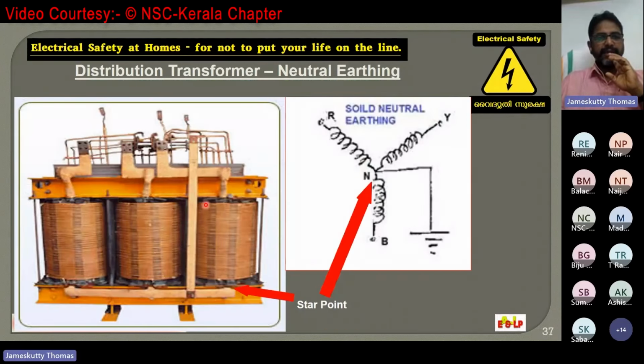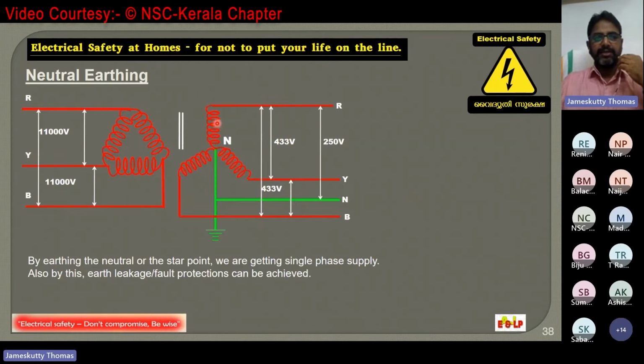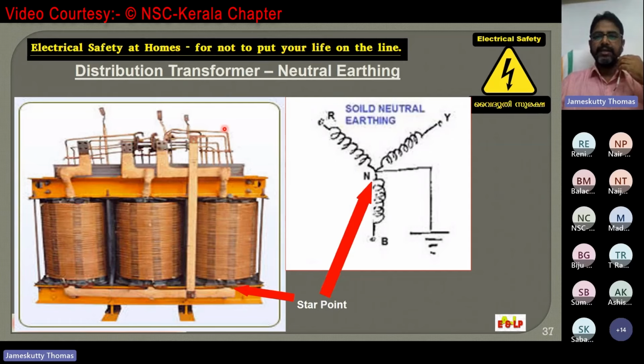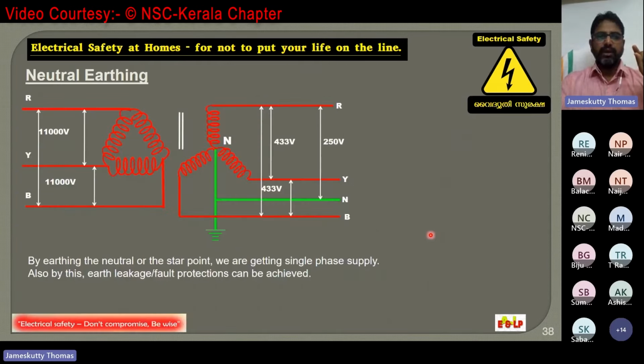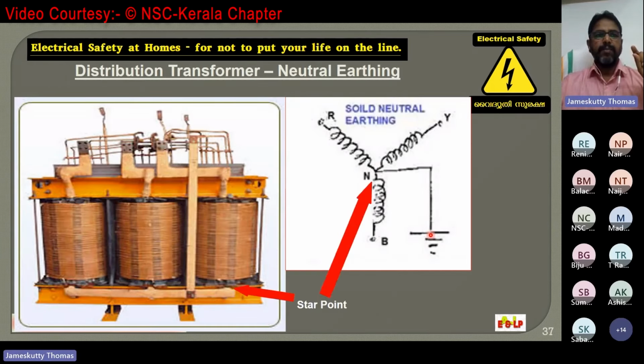See, here the transformer winding is shown. It is opened. The primary winding will be connected in delta, and the secondary winding will be connected in star, just like this is the delta connection and this is the star connection. So on the secondary side, it is connected in star. The midpoint of these connections is called the star point. That star point will be earthed, and that earthed star point is taken outward as the 4th wire, and it is called the neutral.